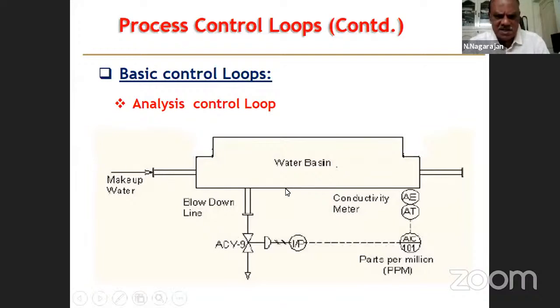So makeup water is here. From the cooling tower sump, the sample is taken and analyzed, and the analyzer results are passed through the transmitter and then go to the analyzer control. The dosage is in parts per million; usually these are very small doses. So that is the blow down. When the chemical concentration is more, it starts discharging a certain quantity of liquid, and you add fresh water. Okay, this is the cooling tower circuit.